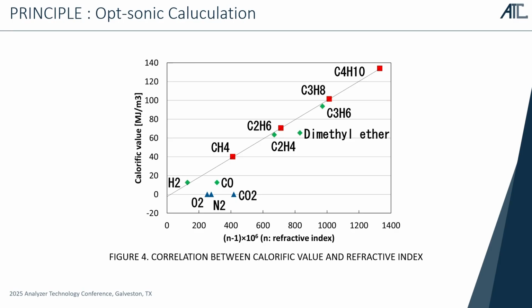And then this is the sensitivity of the optical sensor. So as I mentioned, if we know the refractive index, there is a relationship with the BTU value. So, for example, this is methane, pure gas, 100% methane. So the refractive index is like a 400. So if we measure the 400, the device indicates like a 40 megajoule, which is about like a 1,000 BTU.